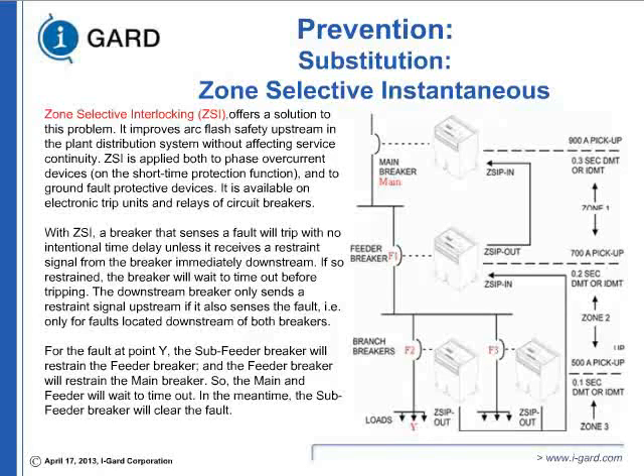You don't have to worry about it. If the fault is upstream of the lowest device, the lower device does not see it, so the upstream device will quickly trip. The only disadvantage of this is it's very hard to retrofit unless you have the foresight to buy equipment that's conducive to zone selective interlocking. This eliminates the additional delay for coordination purposes. Every breaker is set at quick operation if it is in their range.